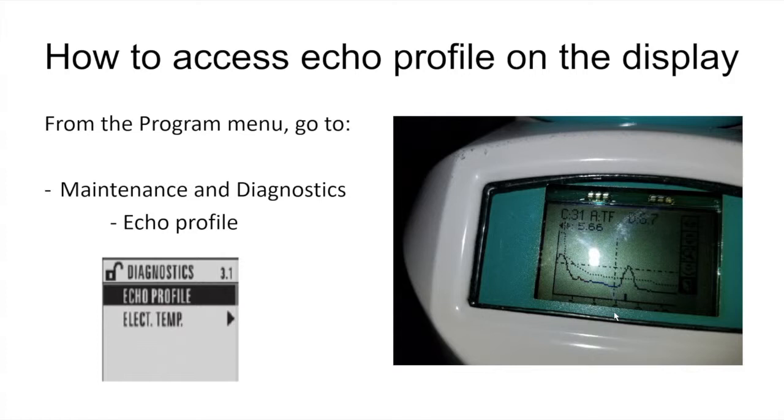Here I'm showing a picture of an echo profile on the LR250 and for that we need the hand programmer. All we need to do is go into the program mode, jog down to maintenance and diagnostics, then to echo profile, and we'll take a look at the echo profile.